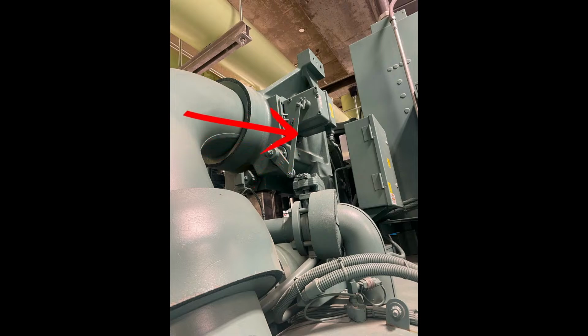And these are just a 90-degree rotation. So that's all you're going to get out of this, and that's all you should expect. As it rotates around, it will pivot up. Like this one, as it spins clockwise, it's going to pick that armature up and slide, in this particular case, a VGD ring out. But the calibration process is pretty similar from the VGD to the PRV, just in a slightly different context. Either way, with everything closed, set your linkage between the actuator shaft and the PRV shaft, and then you just have to stroke it.